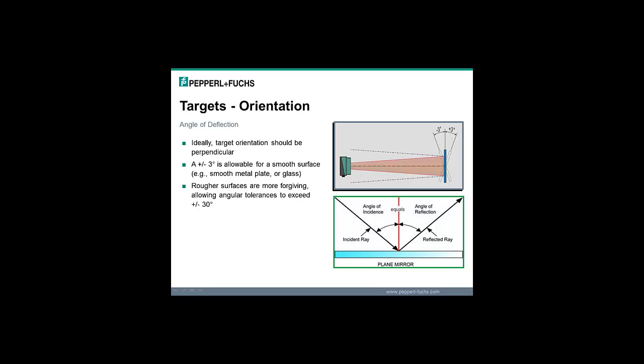This slide illustrates what I spoke of on the previous slide regarding the angle that you can get away with when looking at a smooth target. Ideally, the target's going to be perpendicular, but that's not always possible in real life. So we'll allow up to a ±3 degree target variance, left or right, up and down, doesn't matter, where the target is still going to be detectable if the surface is like a mirror, like a glass, something very smooth. You can go beyond that to 10 degrees, 20 degrees, 30 degrees if it's a rougher surface.